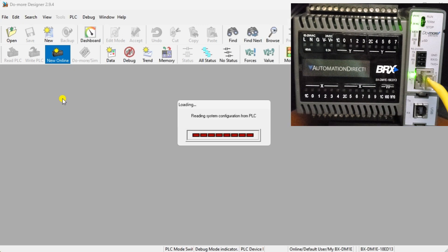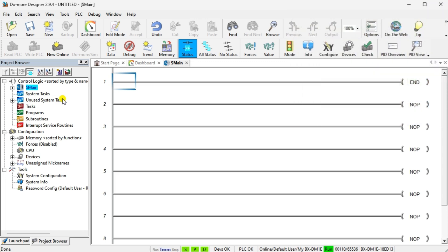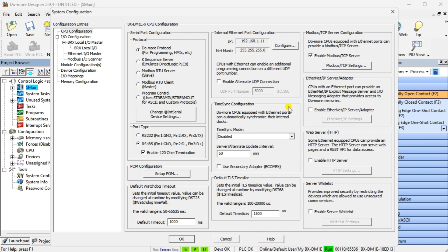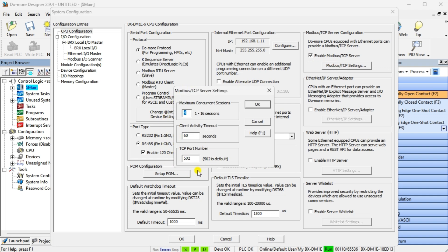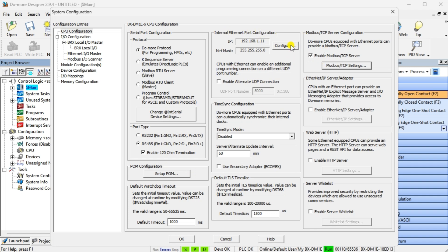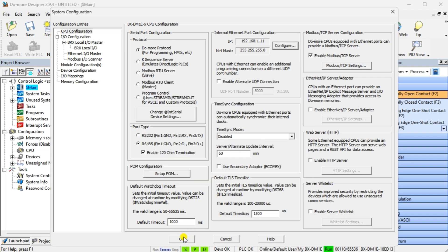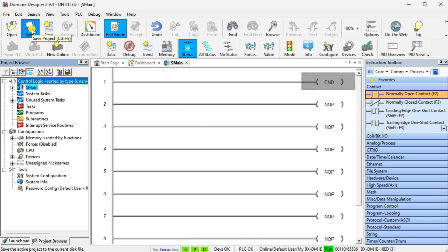Once we've verified that we have the correct PLC to program, we will go to Edit mode and place an End Statement instruction for our logic. Select System Configuration from the main menu PLC or under the Tools menu in the Project Browser. The System Configuration window will now be displayed, showing you the IP address. Ensure that we have selected the Modbus TCP Server option for this PLC. Transfer and save the Modbus Server PLC setup and program.